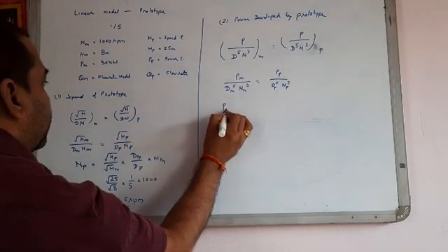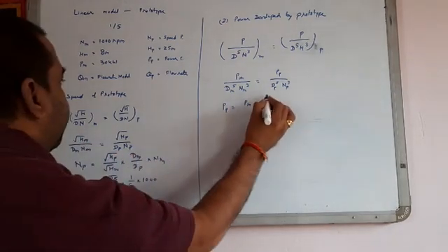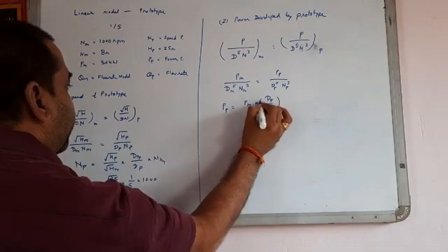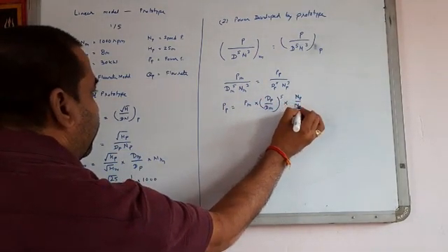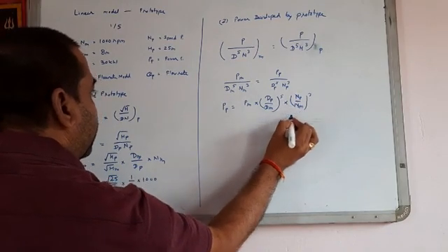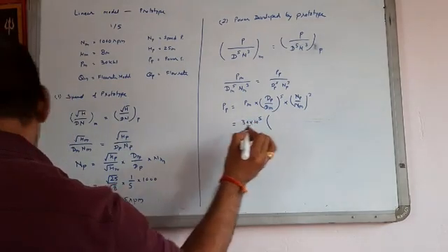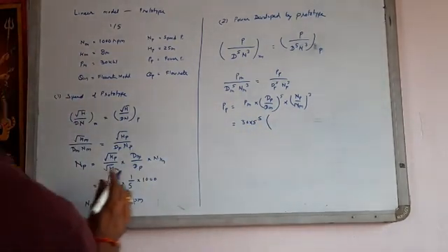Now we have to find out PP equal to PM into Dp by Dm to the power 5 into NP by Nm to the power 3 equal to 30 into 5 to the power 5, and NP by Nm is 353.5 by 1000 to the power 3.